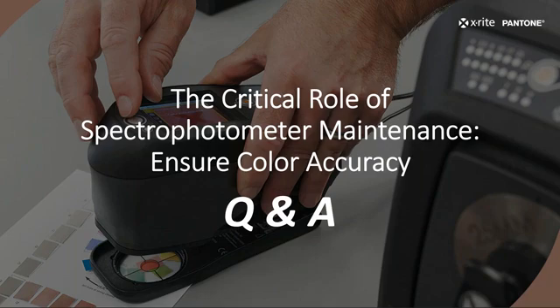Now, even with the dust filter kit, let's be honest, the instrument still has an opening, right? It's where the measurement takes place. So that opening can allow dust to get in as well. But the dust filter kit is for those extreme environments, and it includes everything you need in order to completely protect the interior components. Because inside you've got lenses and detectors and light sources and all those kinds of things, and it's protecting all of those from this dust adhering to them, which is really the culprit.